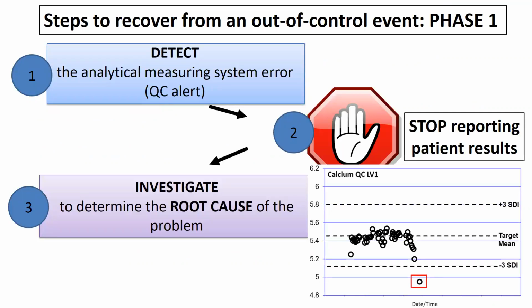So now that we have detected the error and stopped reporting patient results, we can examine the Levey-Jennings charts for the calcium QC as shown at the bottom of the slide. So we reviewed our records and nothing really seems amiss, except for a slight downward trend in QC results over the past couple of days that could be seen on the Levey-Jennings chart.